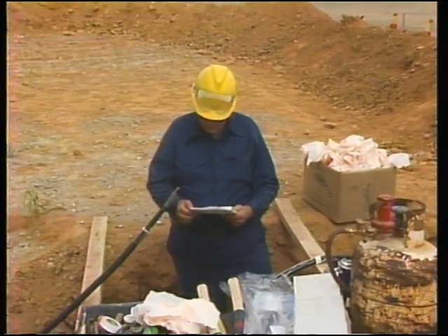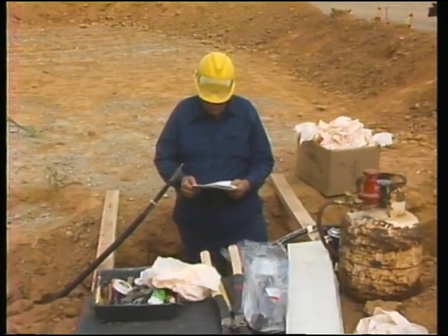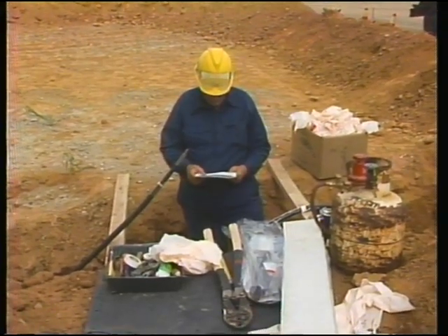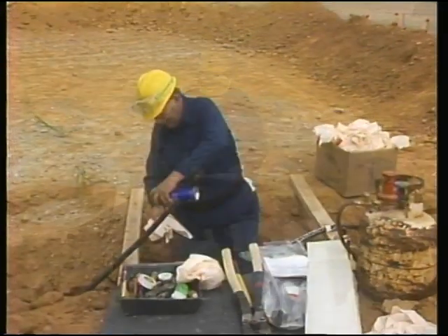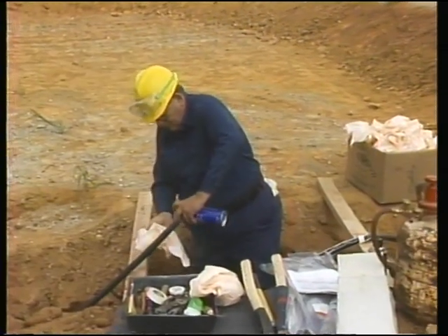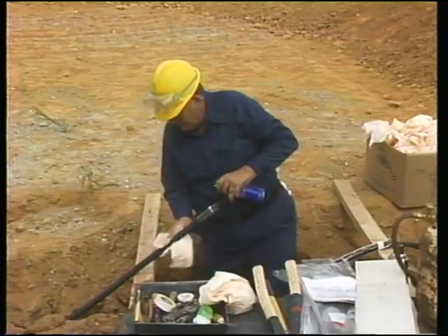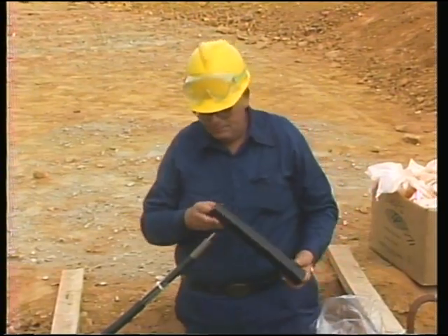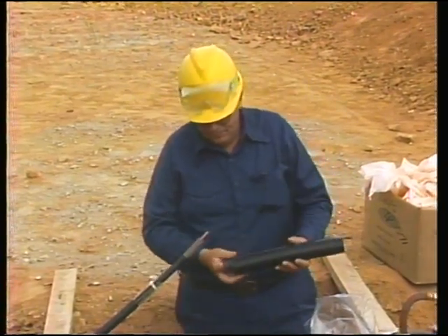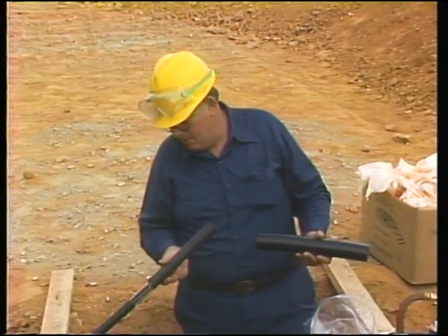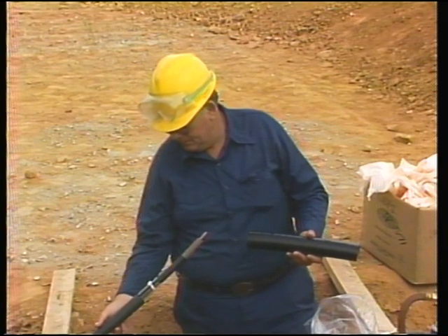At the site, the workman first reads the splice kit directions carefully to familiarize himself with the kit and the splice procedure. Then, as before, the cable is cleaned with cable cleaner and a clean cloth. In addition, the cable ends are prepared according to the splice kit instructions. Before the connector is compressed, the tubes are placed over the conductors.